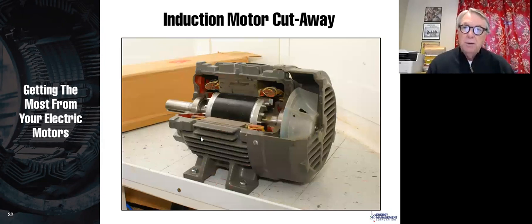This is a real motor, and you can't see the rotor bars because they're in the middle of the iron. You always need iron to conduct magnetic flux, just like you need copper or aluminum to conduct electric current. So in this case, we have an aluminum rotor, and the aluminum rotor bars are going through that iron. So here's your stator winding. Here's your end rings. You see these end rings are big, and they mold a little fan into the end rings. And then the aluminum bars are going through the middle, but you can't see them.